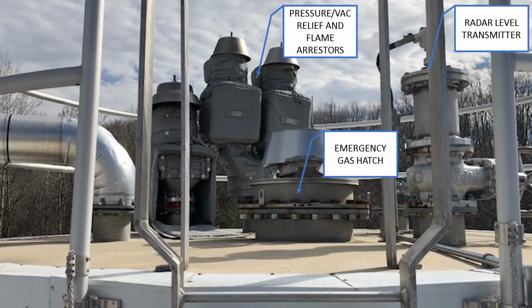If all these fail-safes were not to work for us, there is an emergency gas hatch. It's just a large cover that will pop if we ever exceed 13 inches of water column within the digester. This is the last line of defense, so something we never want to see going off. And we also have a radar level transmitter on each digester to make sure our levels are being maintained, and also to help us during a takedown of a digester to understand that our levels are below the side hatches to make sure we never open a hatch and make a big mess in the yard.